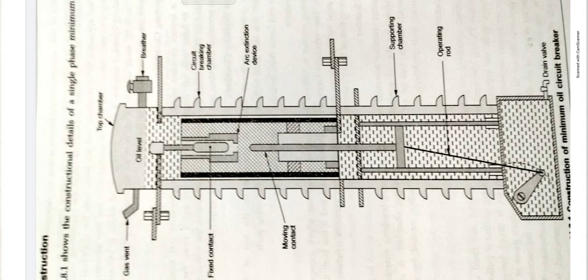Now let's see how we maintain this type of oil circuit breakers. The maintenance of oil circuit breakers consists of checking the contacts and dielectric strength of the oil. After fault has been interrupted by the circuit breaker, fault current flows for short time or load currents for several times. Its contacts may be burned due to arcing.